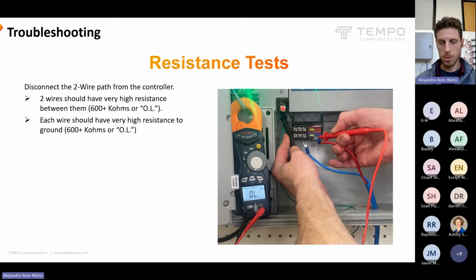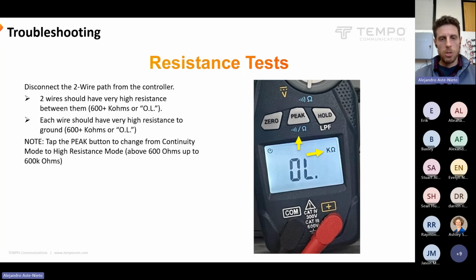So we can take a resistance measurement between the earth and our two-wire paths and ensure that it's a high number. Otherwise, there's a bad splice out there, or there's a nicked wire, or a similar kind of problem. So in order to take a high resistance reading on the CMA 360B, by the way, you will need to take it out of the continuity beep mode, where it's just going to beep at everything under 600 ohms.